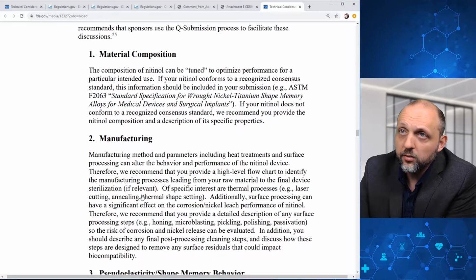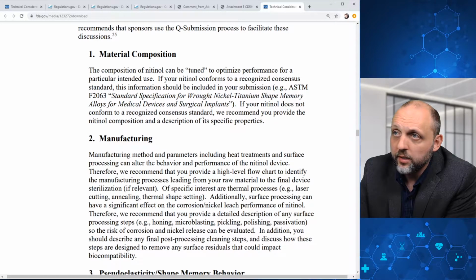So for material composition, FDA wants to understand if your nitinol conforms to a recognized consensus standard, such as ASTM F2063. And if your nitinol does not conform to a recognized consensus standard, FDA recommends you provide the nitinol composition and description of its specific properties.